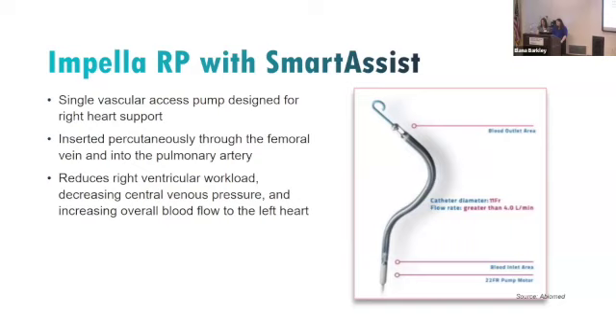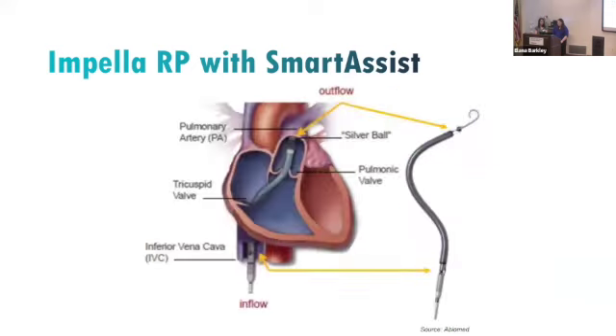It still has an inlet where the blood is drawn into the cannula, and that's sitting in the inferior vena cava at or below the level of the diaphragm. Your outlet area is where the blood exits the cannula. And then it has a dual sensor, comprised of the differential pressure sensor and optical pressure sensor. So these assist in positioning, managing, and weaning of the Impella heart pump. And when it's properly positioned, it pumps blood from the inferior vena cava into the pulmonary artery. This flow reduces ventricular workload, decreases central venous pressure, and increases overall blood flow into the left heart. All right, and here's just an image of it inside the heart.